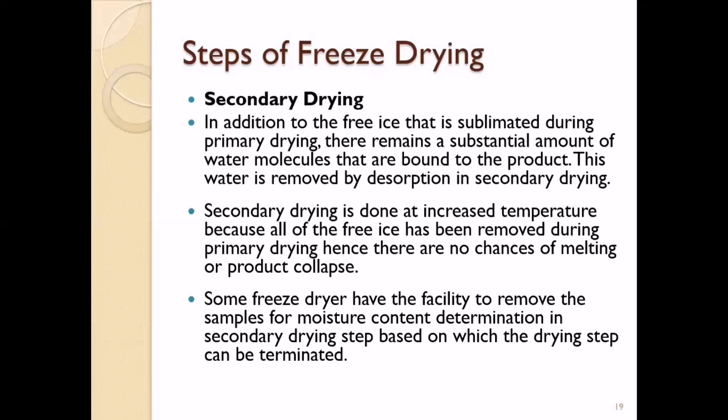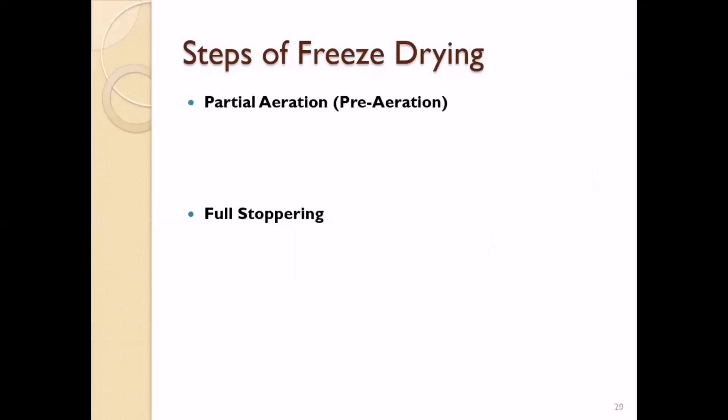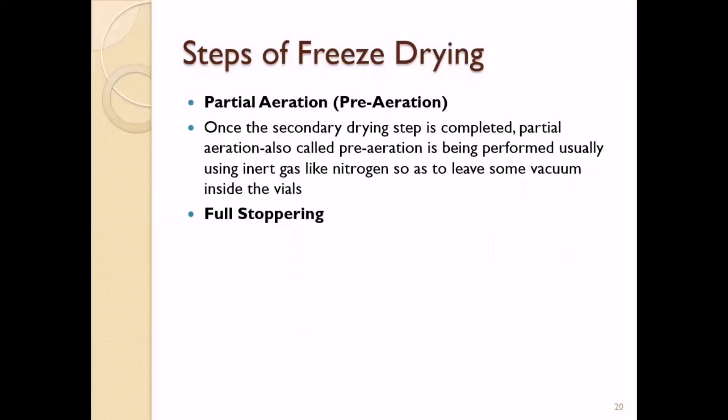At the end of secondary drying, the required moisture content in the product is achieved. Some freeze-dryers have a facility to remove samples for moisture content determination during secondary drying, based on which the drying step can be terminated. Once secondary drying is completed, partial aeration — also called pre-aeration — is performed using an inert gas like nitrogen to break the high vacuum to a certain level, leaving some vacuum inside the vials.